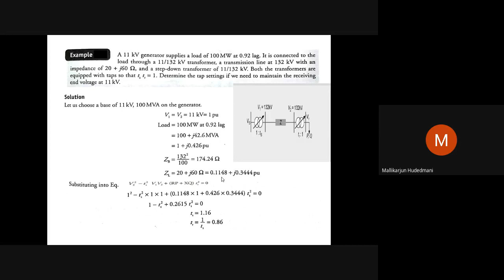Then the values of voltage at the sending end and receiving end are in per unit, and powers are computed in per unit. Then when I want to use this impedance in this equation, which is V2 square minus Ts square, all the values are per unit. That is the reason I have to convert R and X of the given transmission line into per unit. That is the way impedance base I have to calculate. Actual quantity divided by base quantity gives you per unit. Okay? To get into per unit, that is the reason, because all the values are computed on per unit basis only. That is the only reason. Okay?